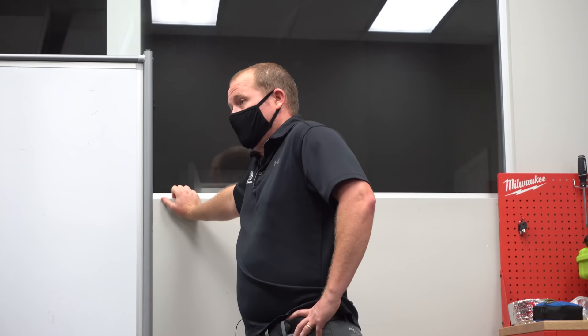If you're going back to a drain cleaning that was done within two or three months, slow your process down. The tech before you probably did a decent flush. There are a lot of cases where it needs more attention. Does it need the drain salt? Does it need to be re-pitched? Are we getting everything out? Is it not being filtered correctly? Is the coil getting dirty? Be really thorough — it's not just as simple as sucking out a drain line every time. Pay attention to the pitch of the drain and whether the drain line is properly insulated. Double traps are common in our market because drains weren't pitched well to begin with and you get sags over time.